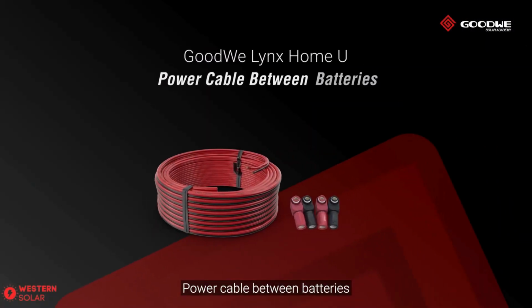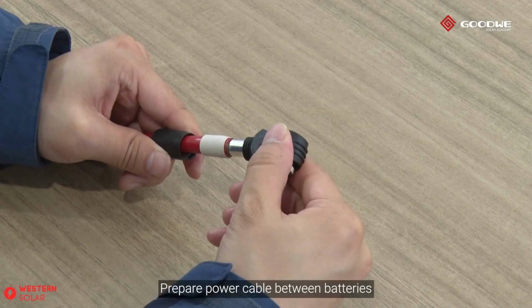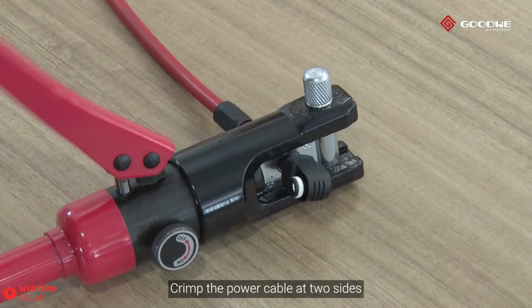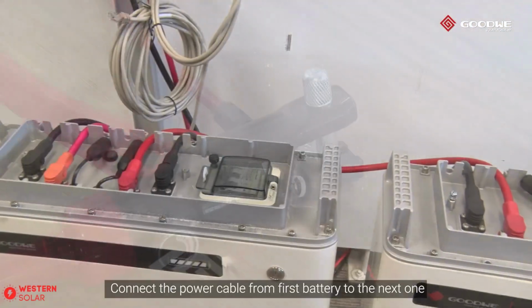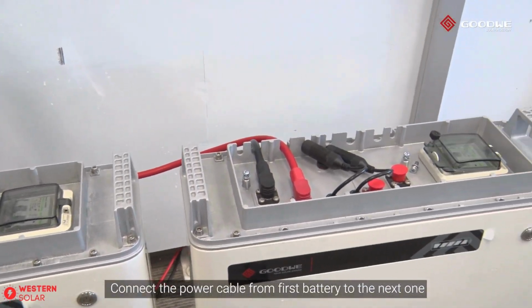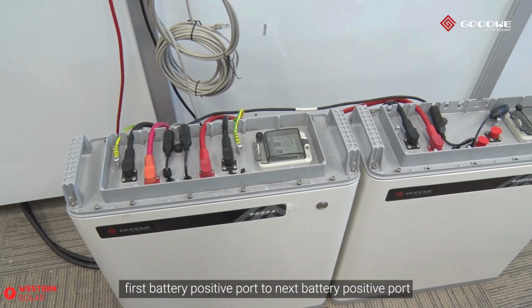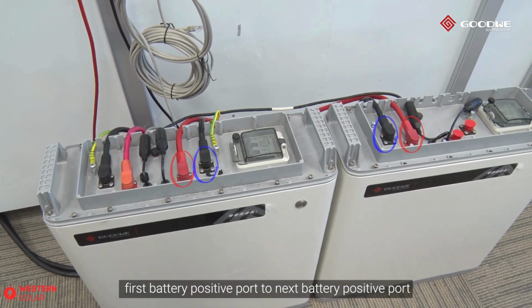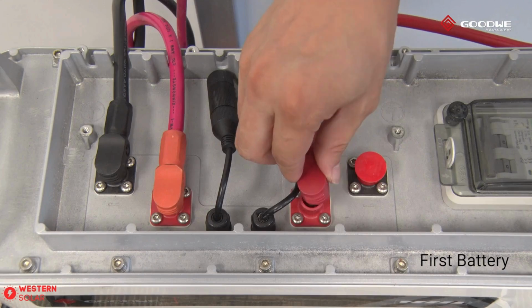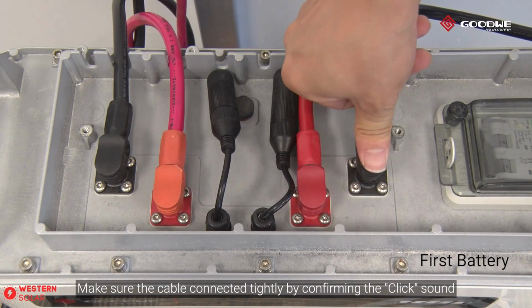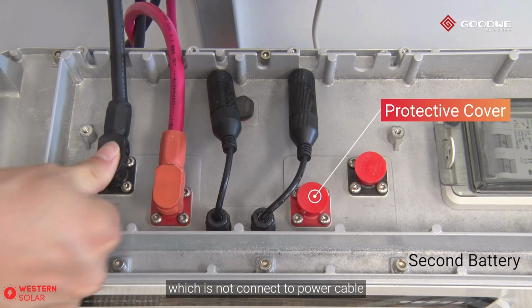Prepare the power cable between batteries and crimp the power cable at two sides. Connect the power cable from the first battery to the next one: first battery positive port to next battery positive port, same for negative port. Make sure the cable is connected tightly by confirming the click sound. Don't remove the protective cover for poles that are not connected to a power cable.